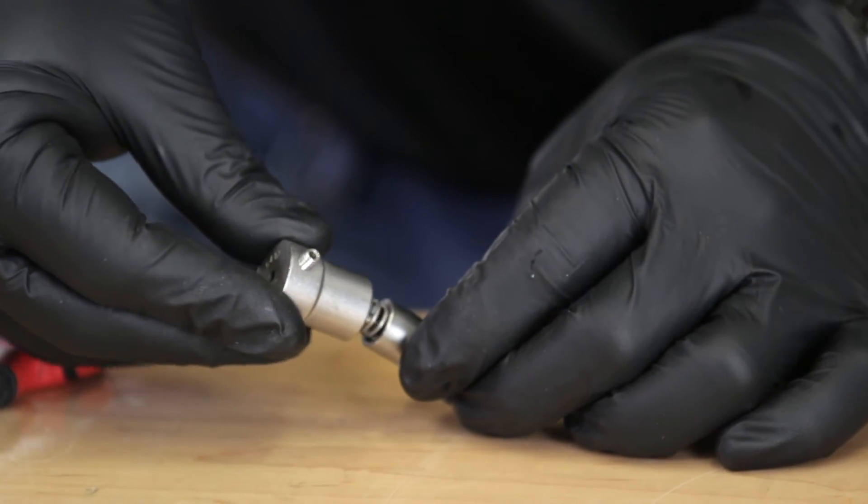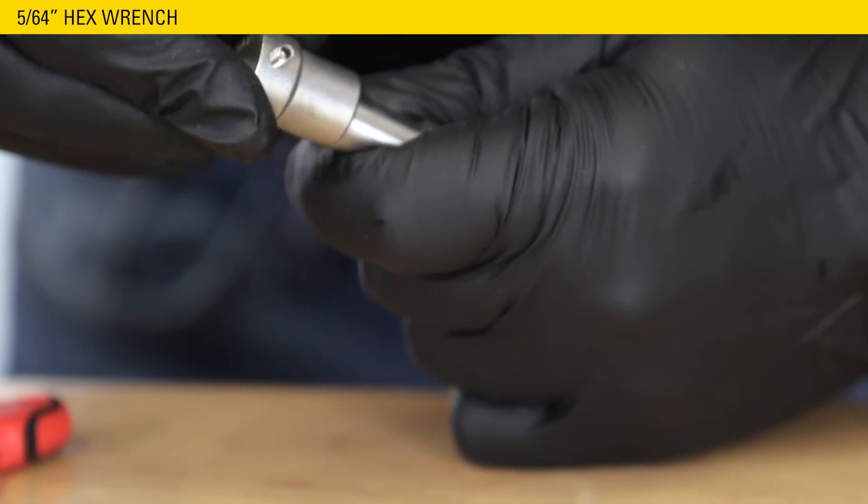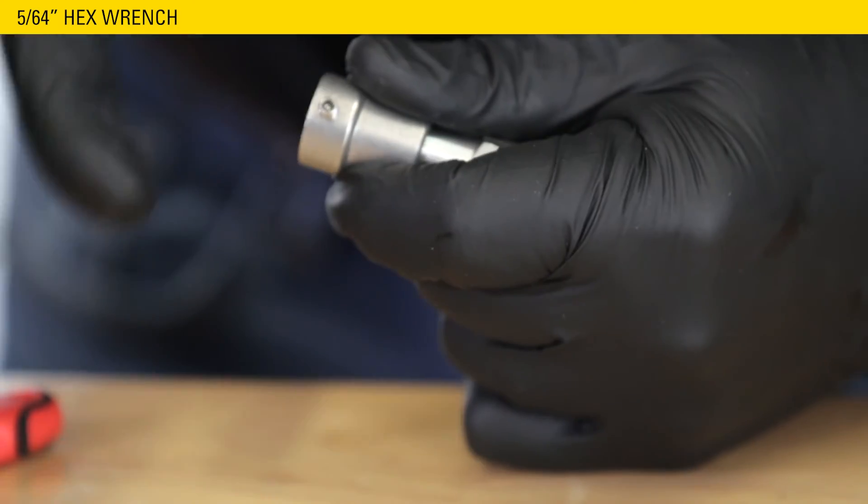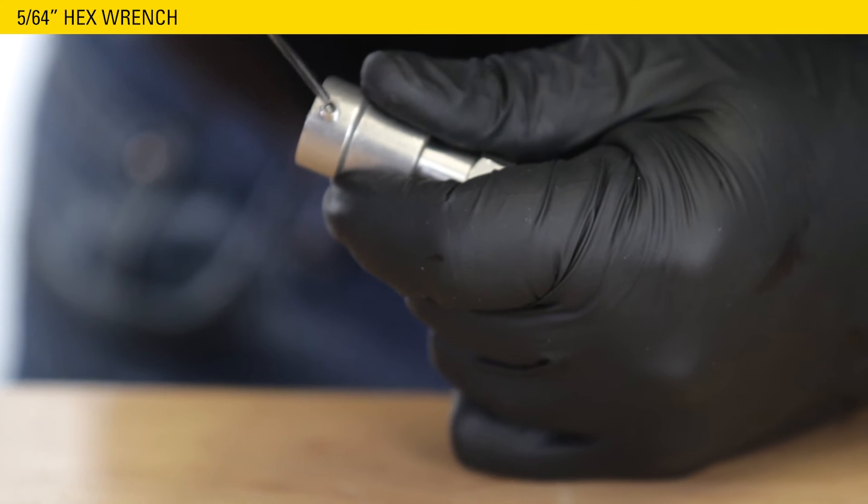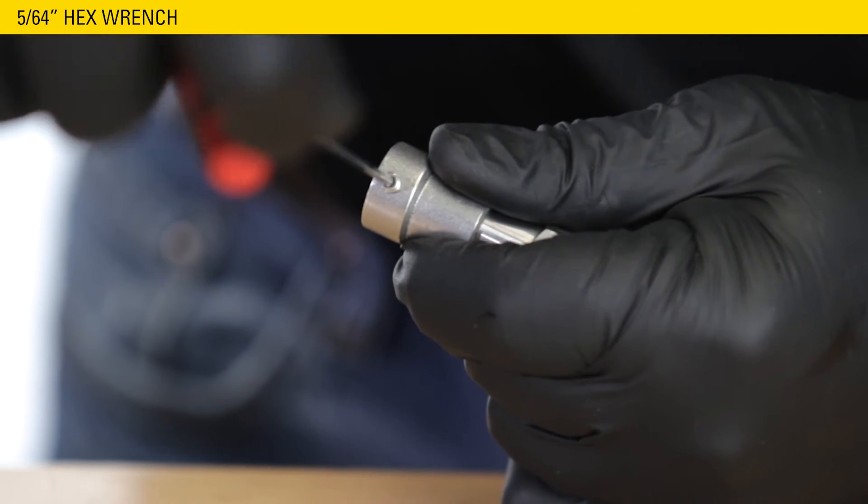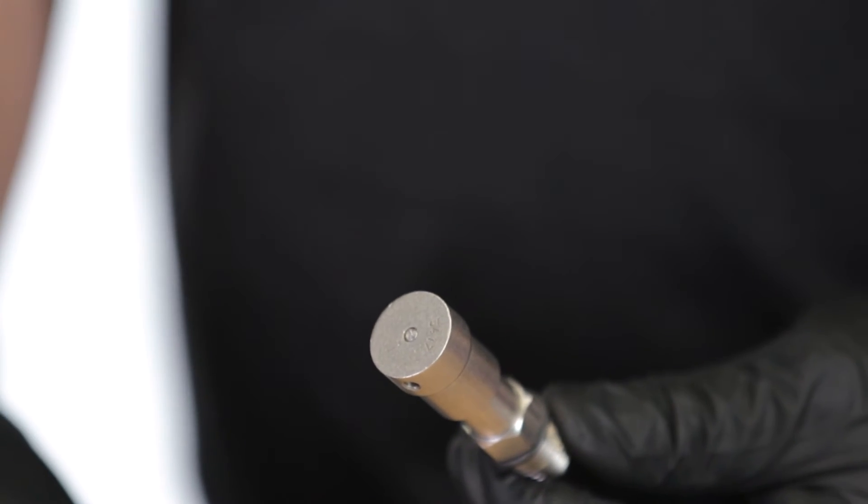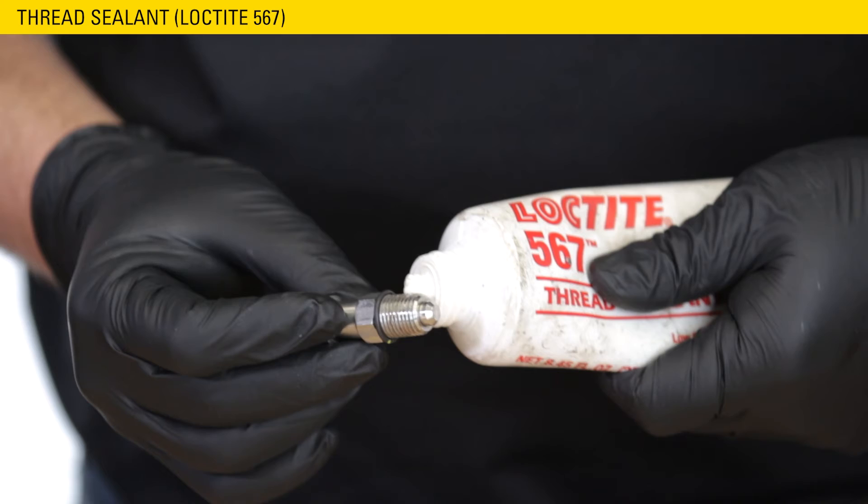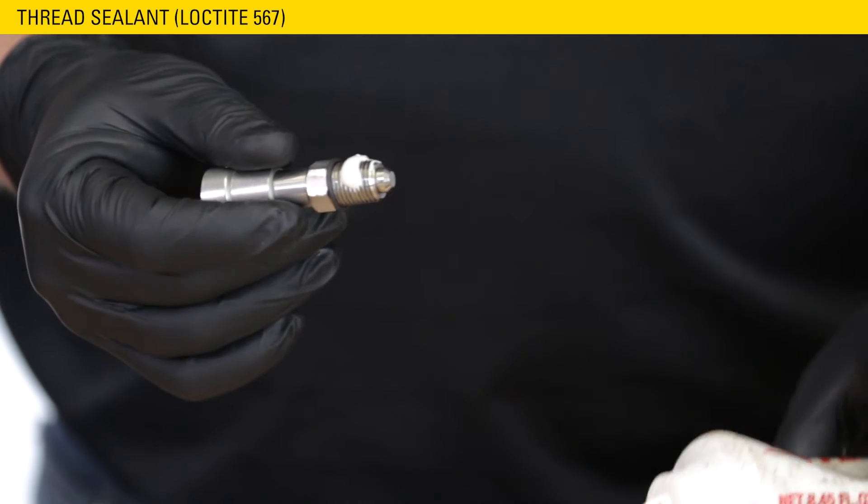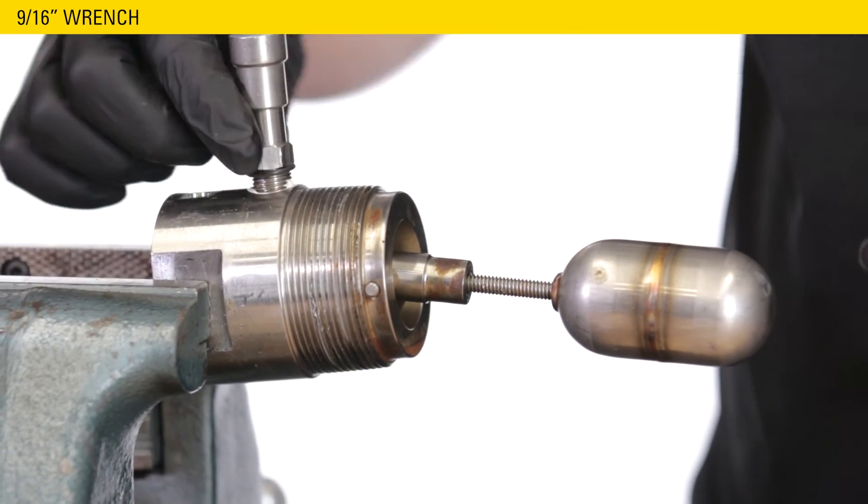Place the cap on top of the spring and compress the assembly to tighten the set screw with the 5-64 hex wrench. Make sure the stem is fully down so the screw catches it. The stem should be flush with the top of the cap. Apply thread sealant to the override fitting threads. Thread the override fitting back into the housing with the 9-16th wrench.